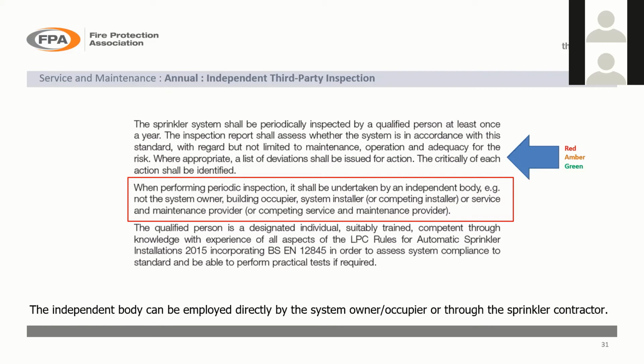If you've got a problem with your water supplies, I'll just give you a typical example of something that's red. We look at your report and see that the system, your pumps aren't working, or your pumps are below duty. That will be flagged up for definite as a red, because obviously if your pump doesn't work or your water supply isn't capable of meeting the requirements, then it doesn't matter how good the rest of your system is, it's not going to operate correctly in the event of a fire. If you've got things like a bit of overspacing here and there, we might raise that as an amber, depends on the criticality of it.